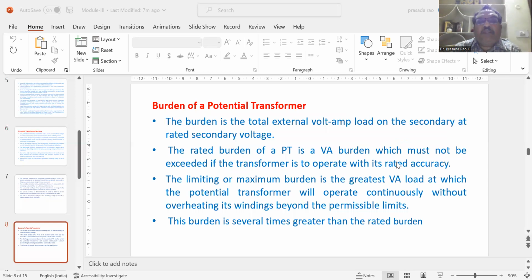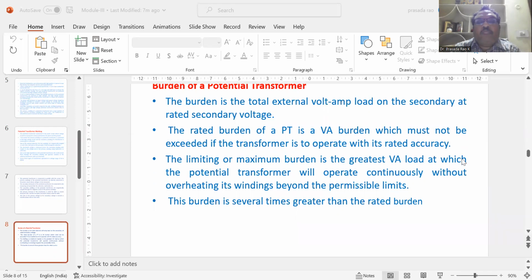Now, the burden of a potential transformer: the burden is the total external volt amperes load on the secondary at rated secondary voltage. The rated burden of a potential transformer is a volt amperes burden which must not be exceeded if the transformer is to operate with its rated accuracy. The limiting or maximum burden is the greatest volt amperes load at which the potential transformer will operate continuously without overheating its windings beyond the permissible limits. The burden is several times greater than the rated burden.